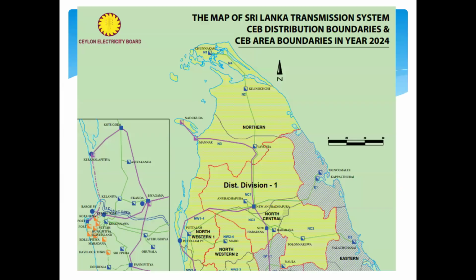So at that time, the system control center switched off some major solar units which feed power into the network. Otherwise, we would have had to trip the line. That line would be tripped due to overload in the reverse direction. So this is the real situation in the network at the moment, not only in the distribution transformers, even in the transmission networks. So this is the place I mentioned. This is the new Anuradhapura substation whose network you have seen. These feeders, the new Anuradhapura to Vavuniya line, were the overloaded line.